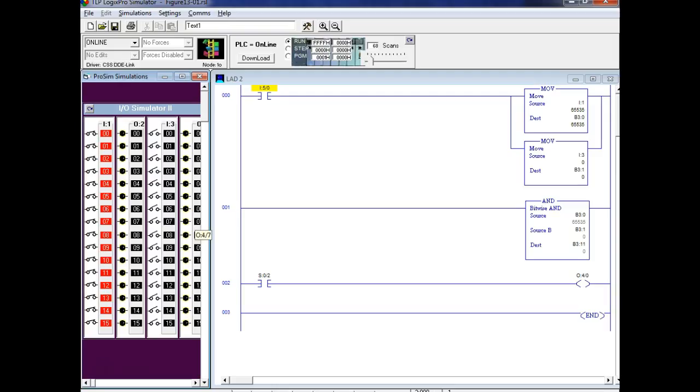So what I was trying to do over here on my RSLogix was come up with a program that says, okay, why would I want to AND? Well, what we can do is set up a mask, and we can determine if that 1 bit inside that mask is set or clear by ANDing it with a mask. But the sign bit, the 0 bit, is not working. So notice, my AND is picking it up. See, it goes from a 0 to 32.